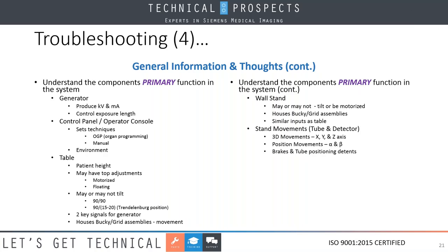from our X-rays. Okay, moving on with this, we have the wall stand. It may or may not tilt, all right? It may or may not be motorized. There's a separate bucky and grid assembly in here with similar inputs to the generator as the table. When we look at the overhead stand, which has the tube and detector, you have 3D movements of X, Y, and Z, and then you have position movements of alpha and beta, which is rotation around horizontal and rotation around vertical. There's also brake and positioning detents that are part of our stand movements.